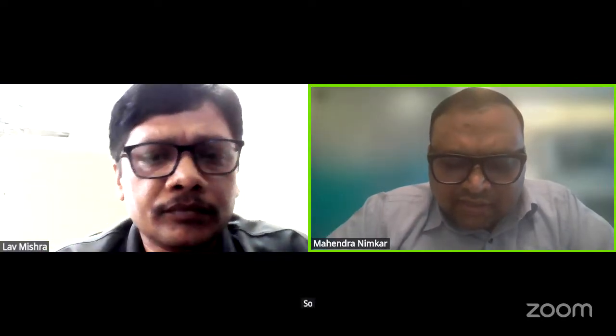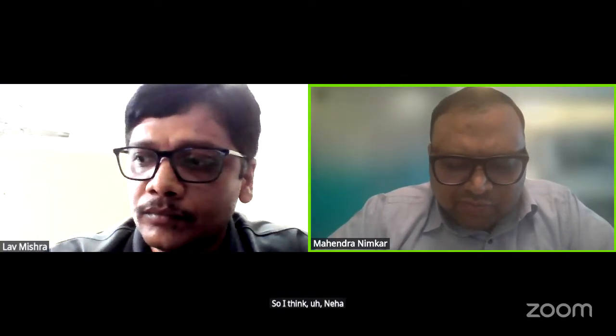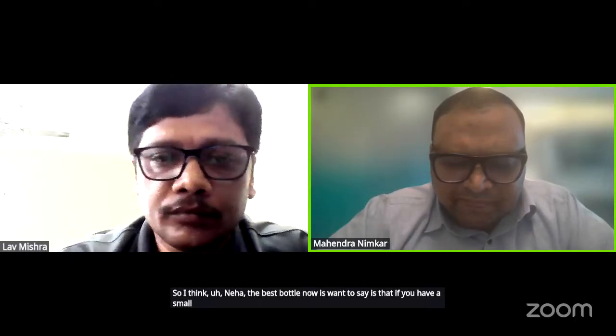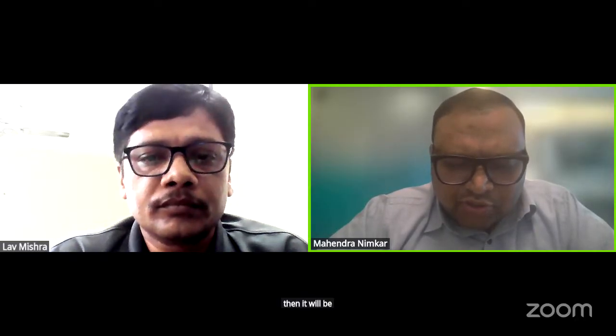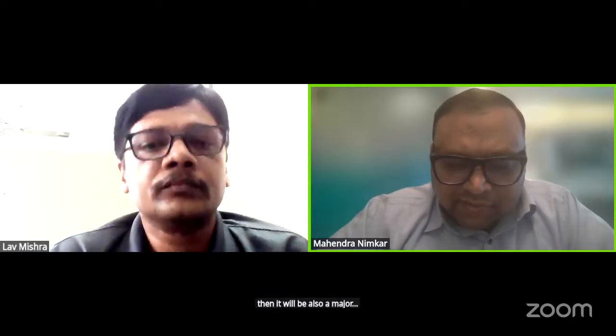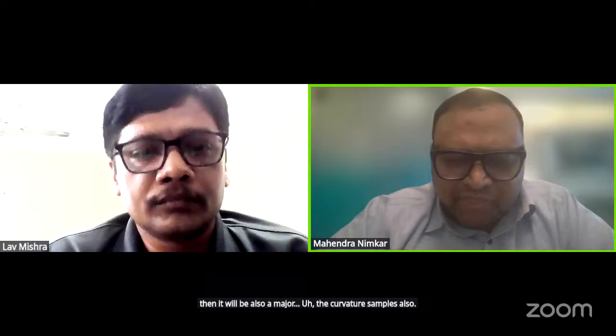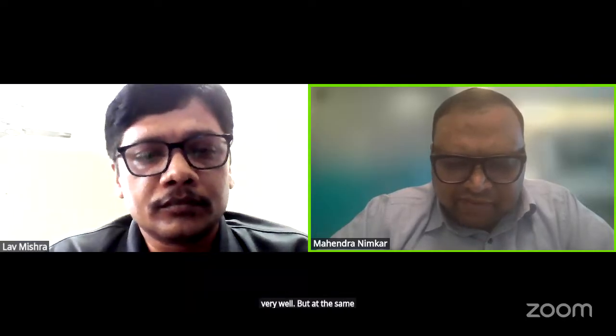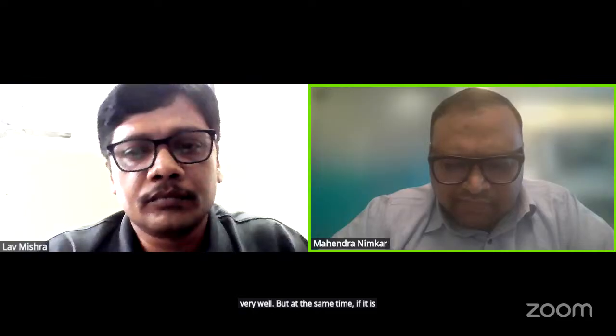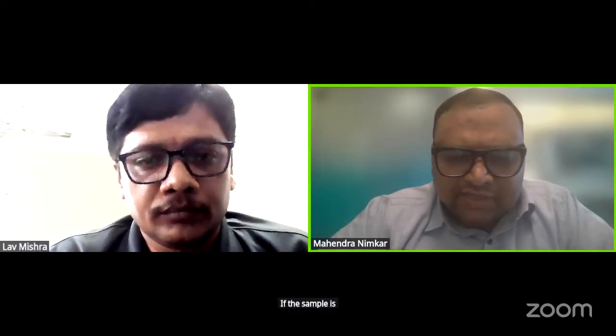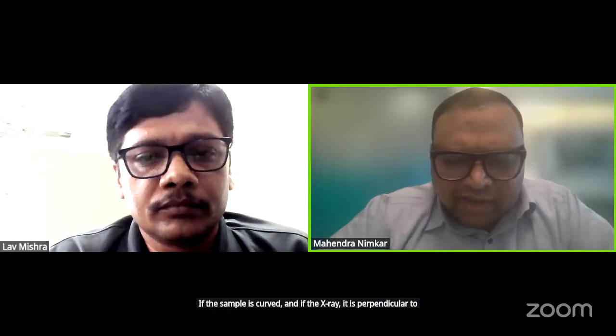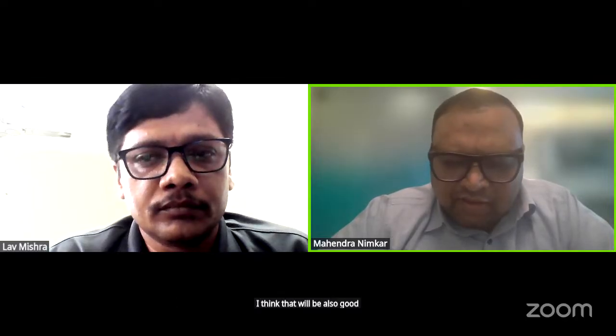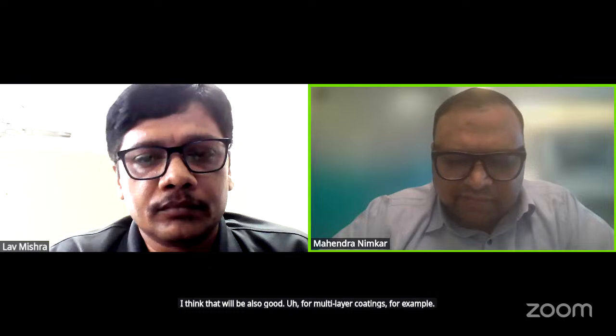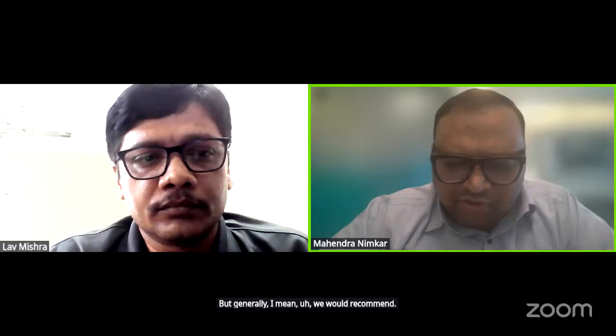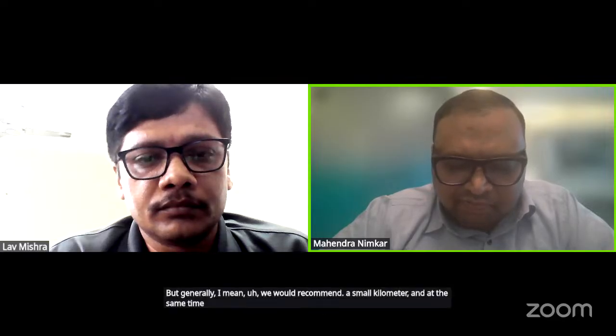So I think, Neha, what Love wants to say is that if you have a small collimator, it will measure curved samples very well. But at the same time, if the sample is curved and the X-ray is perpendicular to the beam, that will also be good for multi-layer coatings, for example. Generally, we would recommend a small collimator, and at the same time, perpendicular should be better.